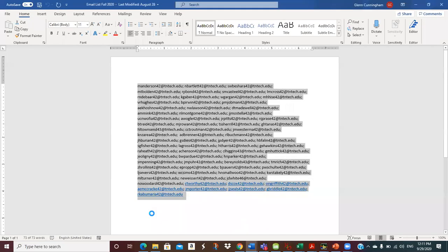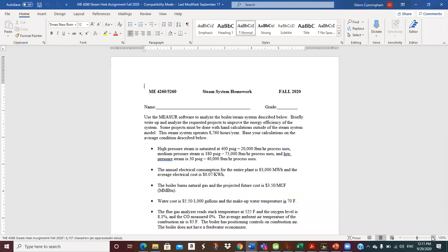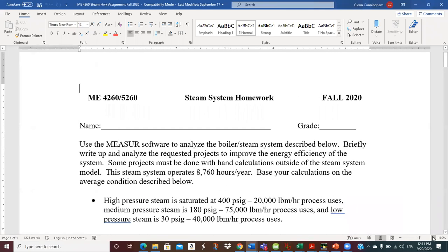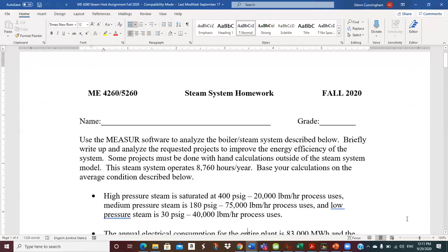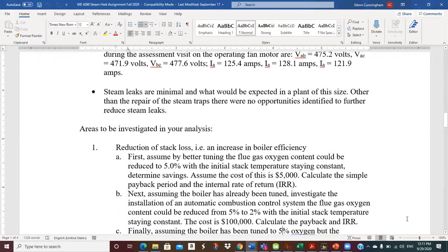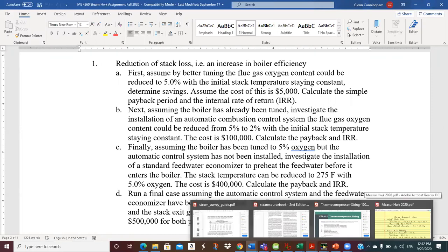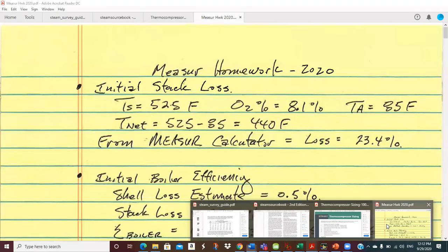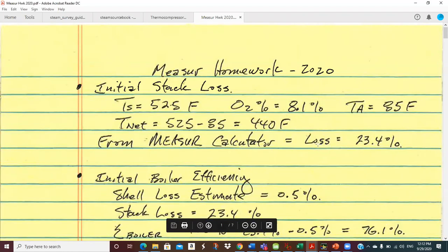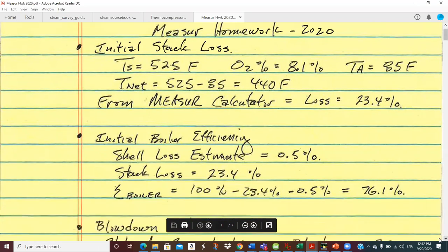There it is. So I think everybody's probably pretty familiar with the input information. We can go back and look through this if we need to, but let's go down to the things that were requested. So the first is stack loss reduction — we're at 8.1% oxygen, 525 on stack temperature, 85 on ambient temperature. That's where I'm going here. There's a summary of it, and that's what I came up with for the original stack loss: 23.4%.